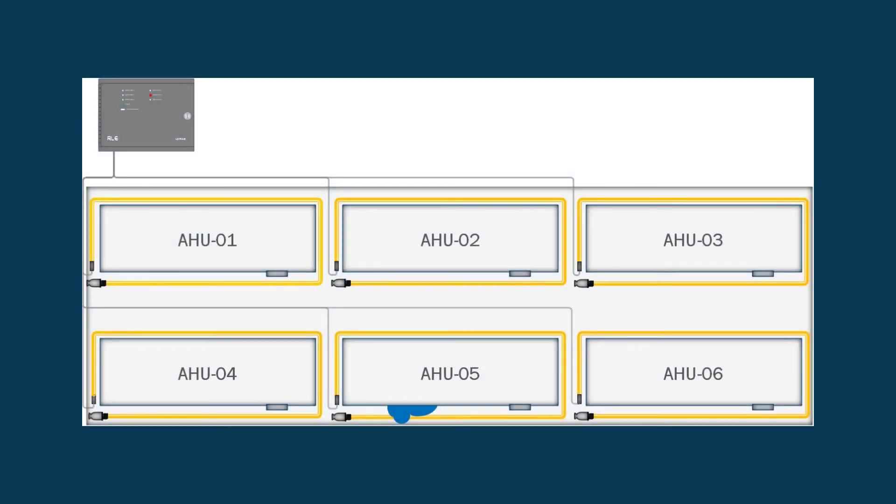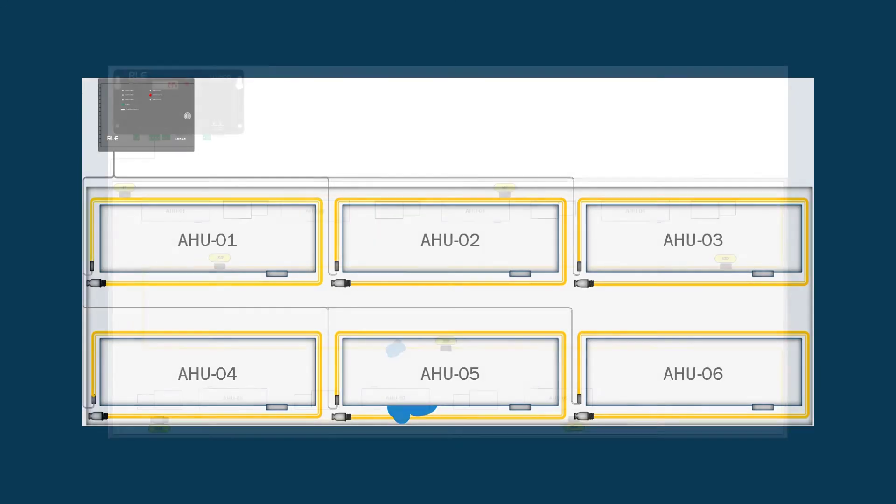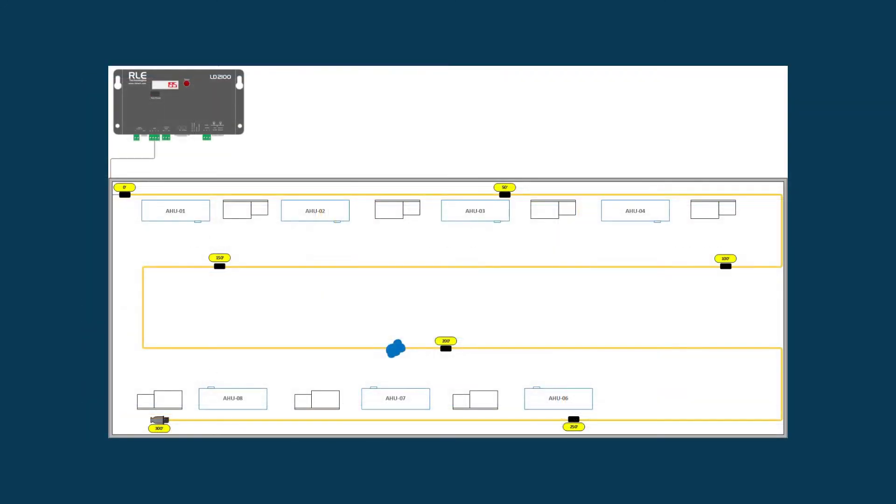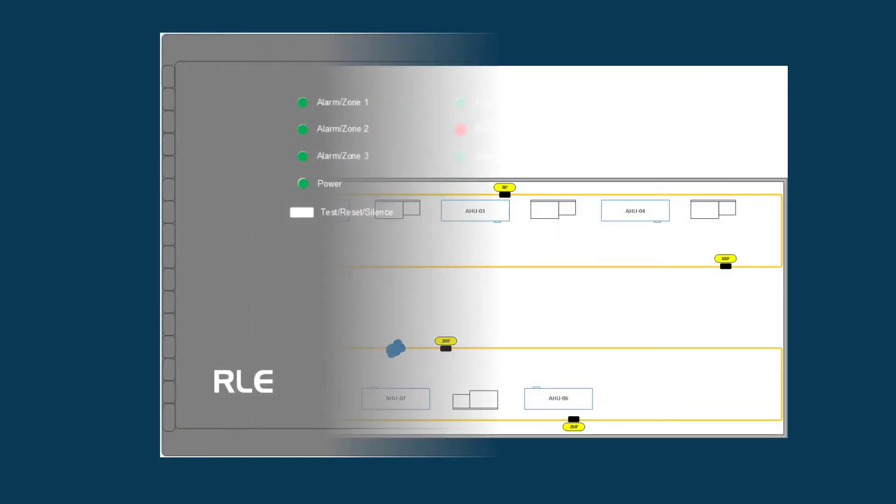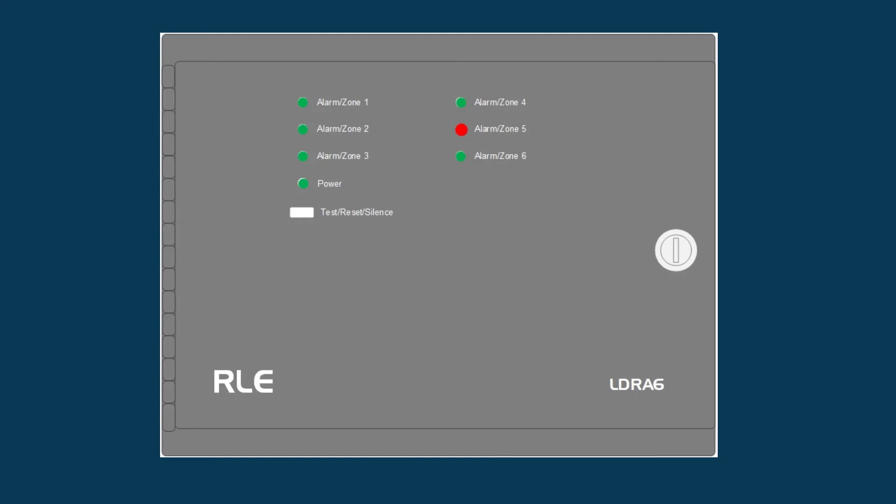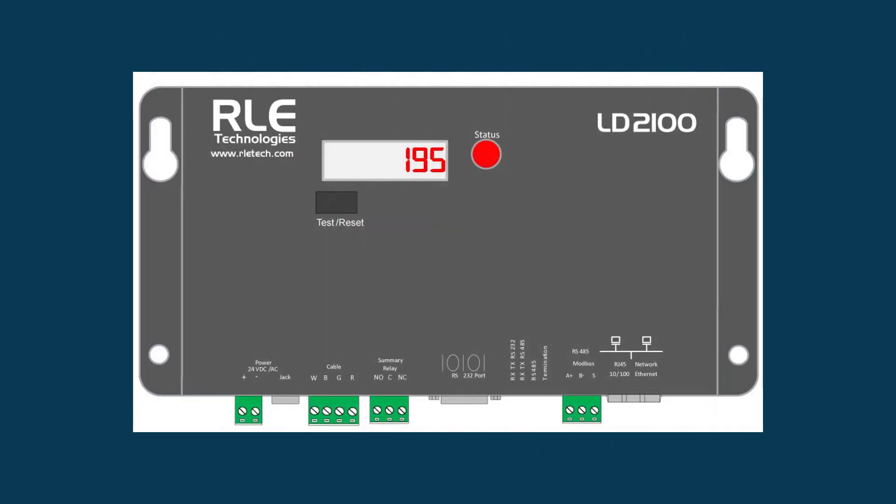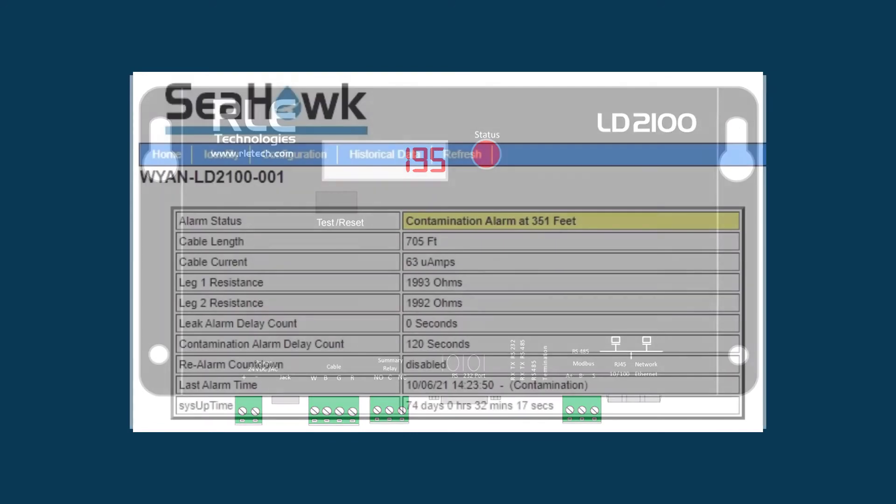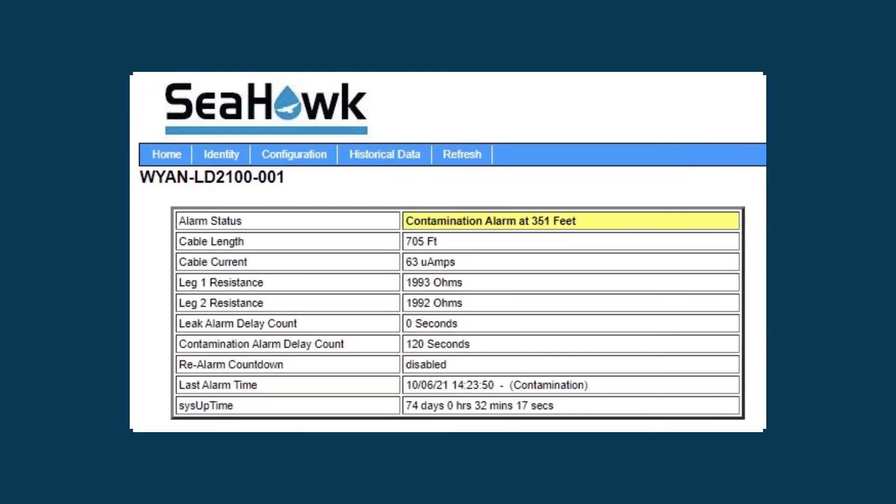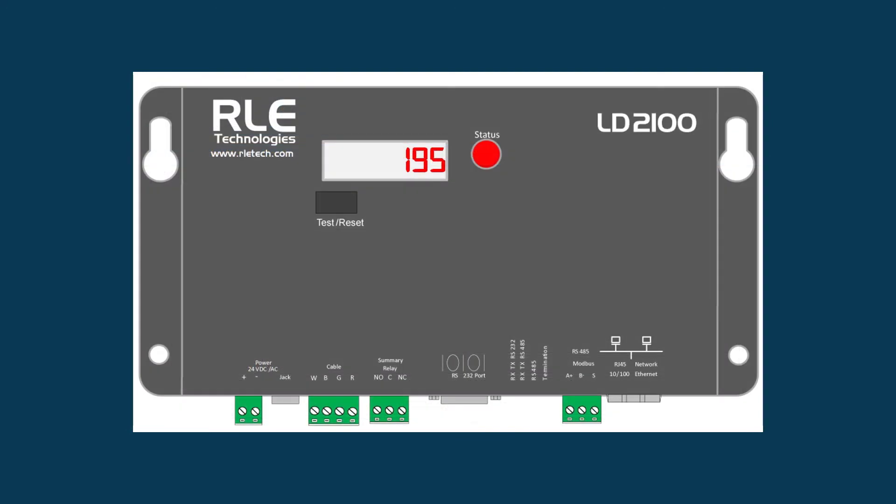Sensing cables also work with these style of controllers. A zone system is a simple go-no-go style of alarming. These style of controllers work ideal for small, isolated areas where distance read controllers show a physical distance to the leak location. They can also display a distance marker if the cable is starting to become contaminated.